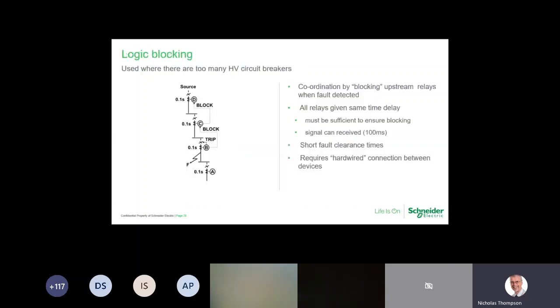Now, when you've got loads of circuit breakers, and I'm going back to an earlier example I was showing, where we had 4 circuit breakers in one circuit, and I was highlighting the fact that the curves may become too close together and we may not have any safety margin. There is a trick up the sleeve where you can hardwire the relays together. Admittedly, it's another piece of the installation that would need to be taken into account, but you can now set all your tripping times to be exactly the same, but you need to program the logic into the relays to trigger the blocking signals to prevent the upstream circuit breakers from tripping when they should remain closed.